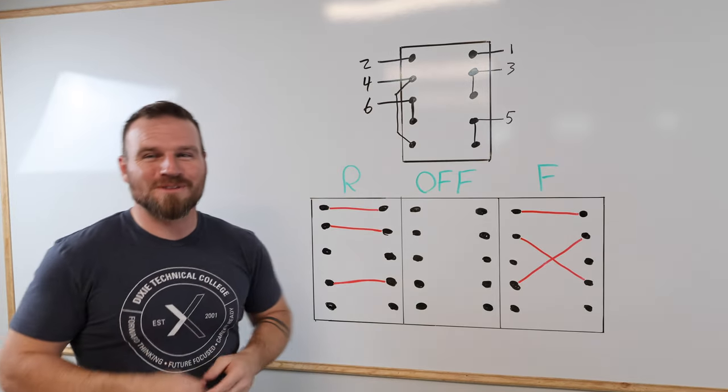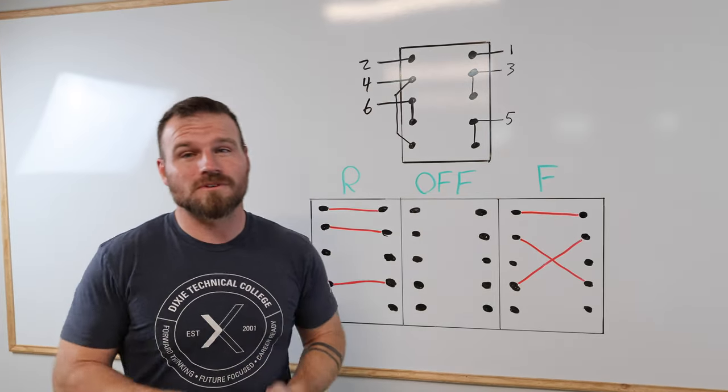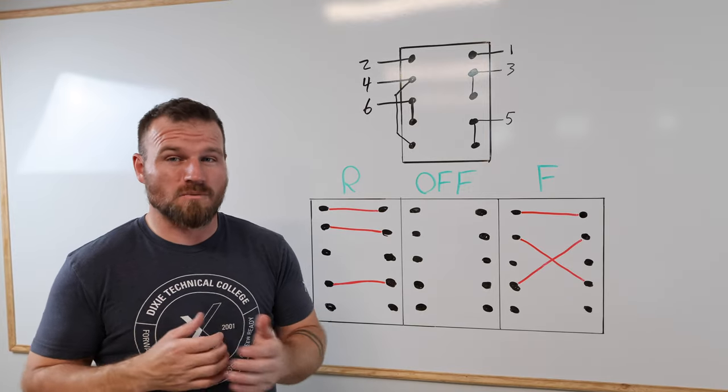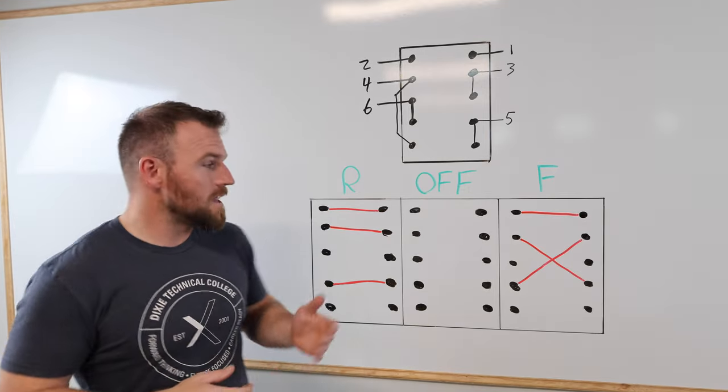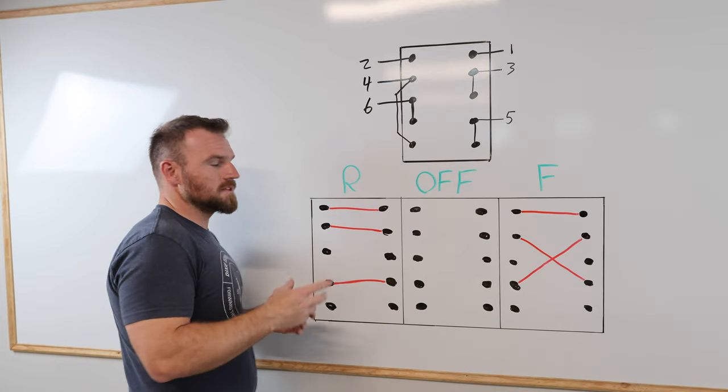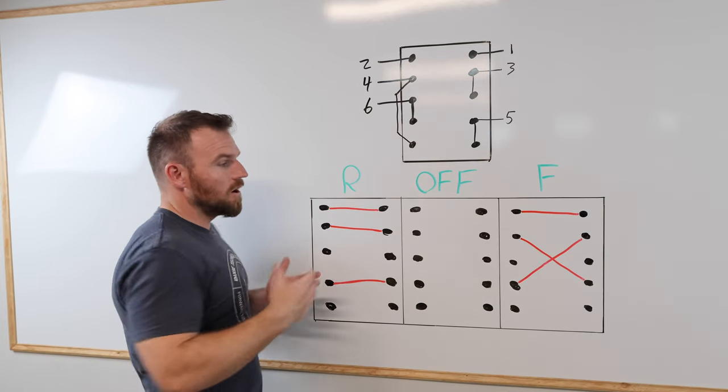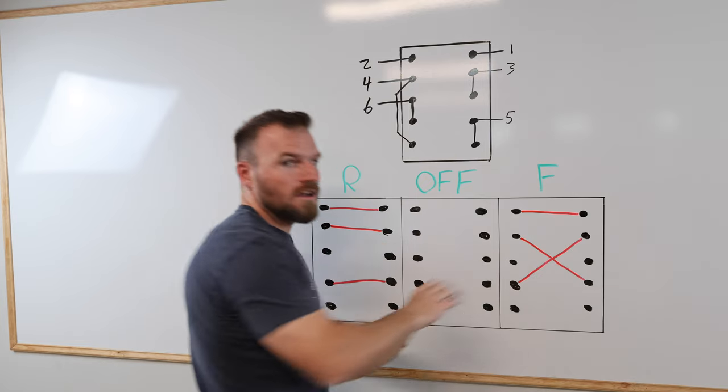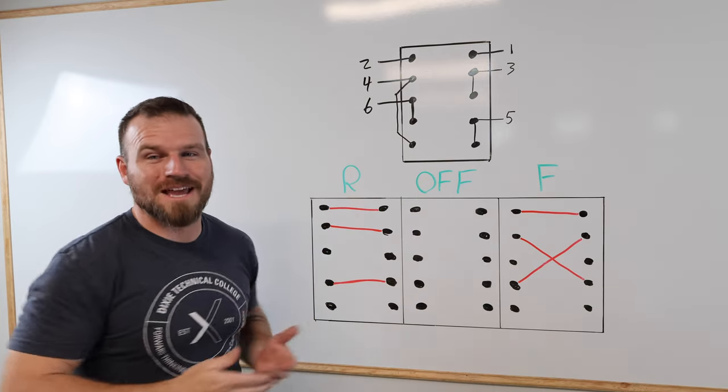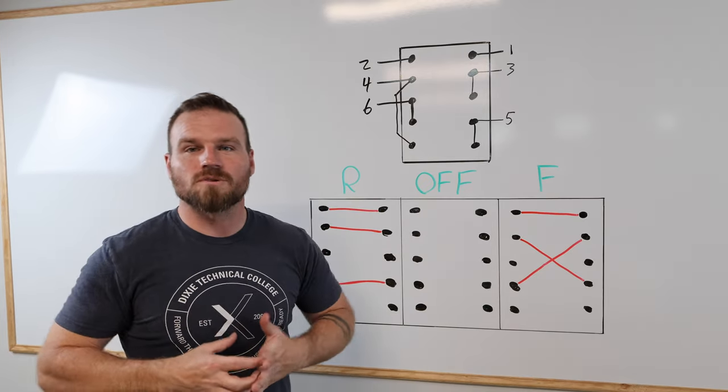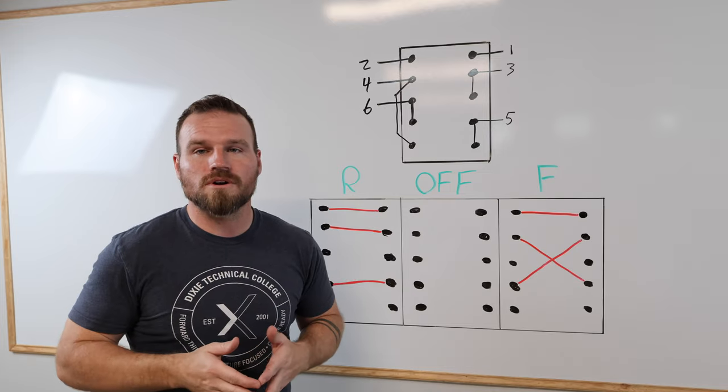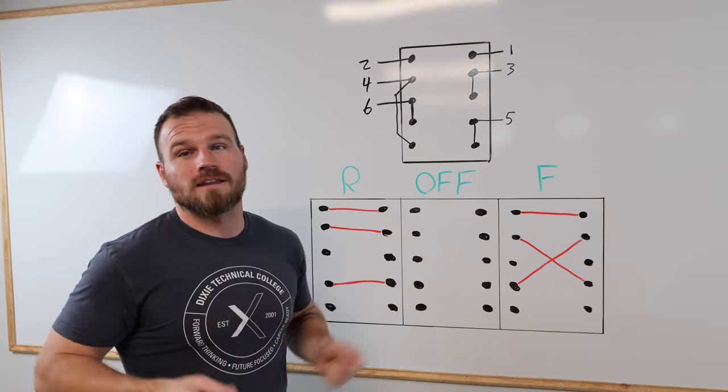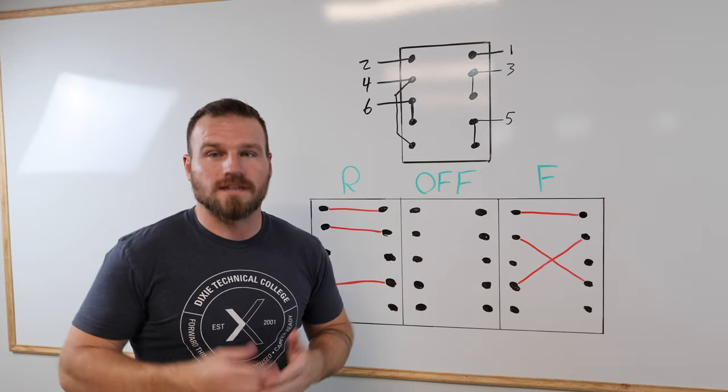Now when we're working with 120 volt motors, or 220 volt motors, we know that we can't just swap the polarity. We actually have to go in and change some of the wiring internally. And we're going to be using some of these contacts to do that work. Ultimately, it really comes down to the contacts here and here, which are the same contacts to do that switching. So what I want to do now is I'm going to show you guys the motor, we're going to talk over the schematic on the nameplate of the motor, and then I'm going to go ahead and show you how we'd wire these two things together.